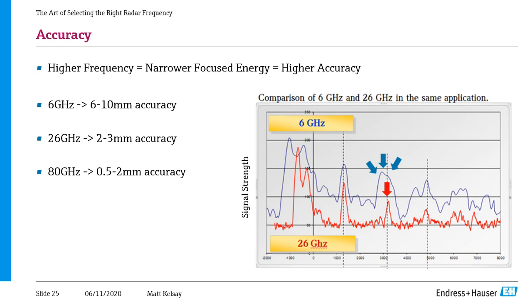And you can see the reflection you get from a 6 gigahertz radar is a very broad peak. So now the radar has to take this broad peak and pick a point along the peak. Your left to right x-axis is your distance away from the unit. The device now has to pick a point along that peak that the actual level is at. That's where you end up getting the 6 to 10 millimeter accuracy with a 6 gigahertz radar.